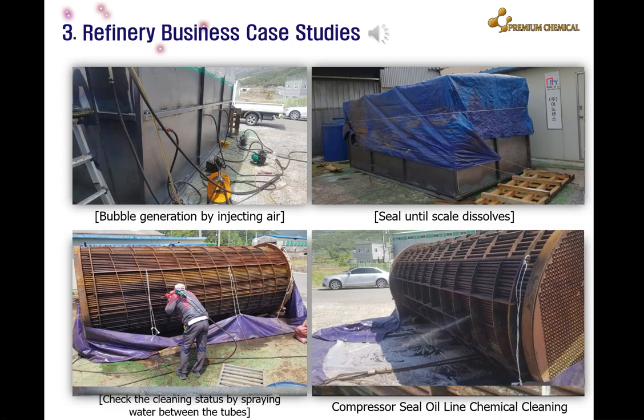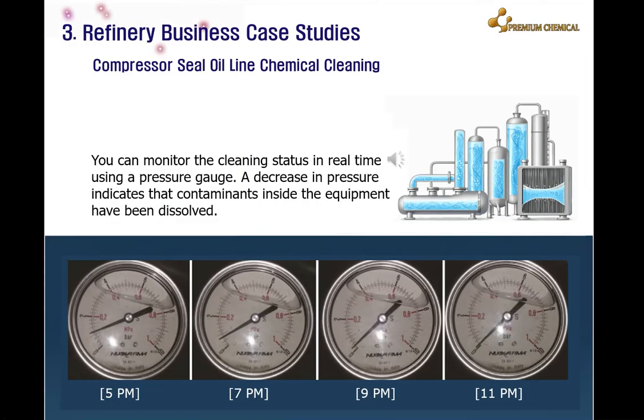Finally, to check the cleaning status of the heat exchanger, a pressure washer is sprayed between the tubes and the high-pressure water is discharged from the opposite side. This indicates that the butadiene, which was tightly trapped between the tubes, has been completely removed. If you want to check the washing status in real time, you can install pressure gauges at the inlet and outlet of the target equipment and check the washing status in real time through pressure drop or pressure.